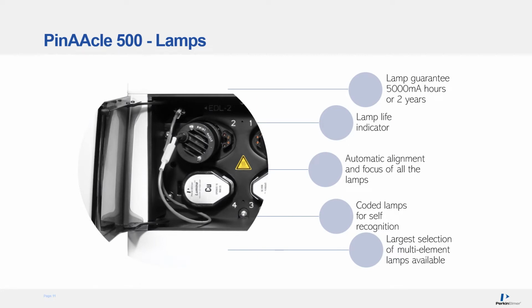One of the other aspects that makes the PinAAcle 500 unique and quite usable is that the lamps are very user-friendly. They come with a 5,000 milliamp hour or 2-year warranty. They all have lamp life indicators within the software. We do sell coded lamps for self-recognition, so the software will pick up what lamp is plugged into which location within the lamp turret. We'll also be able to identify that lamp by its serial number and tell the user how many milliamp hours are on that lamp. We also have a very large selection of single and multi-element lamps available within PinAAcle to help you meet whatever needs you have for elemental analysis on your flame AA.